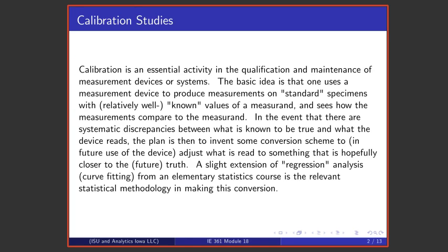Calibration is an essential activity in industrial use of measurement devices or systems. The basic idea is that one measures a known with a device that one wishes to improve the accuracy on. One has some kind of standard that is traceable ultimately to an organization like the National Institute for Standards and Technology. The idea is to figure out how to convert what is produced by the measurement device to something that is close to the truth for the standard. The methodology that gets used is regression analysis or curve fitting, and that's what we're going to use in this module.